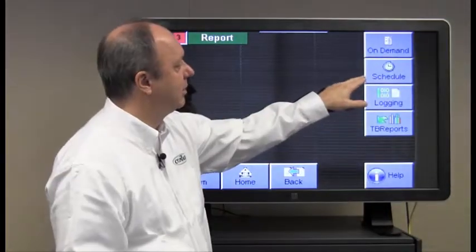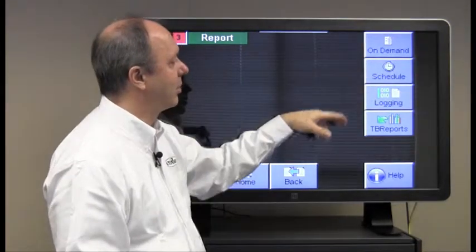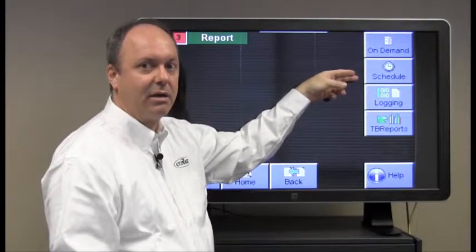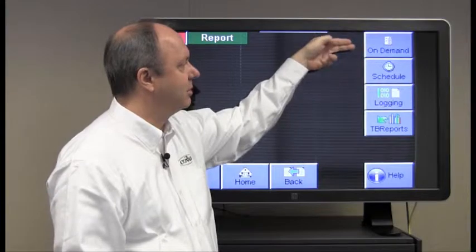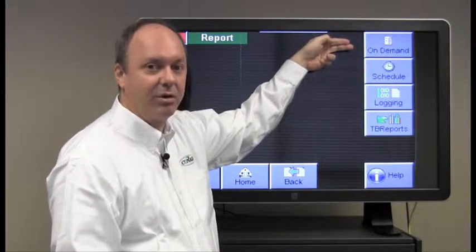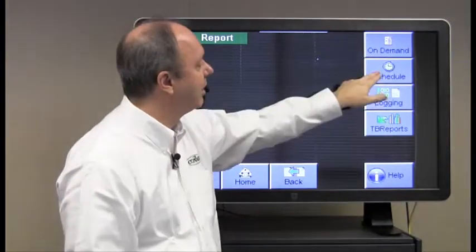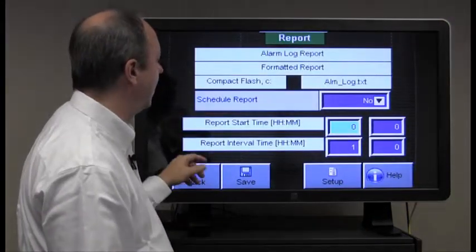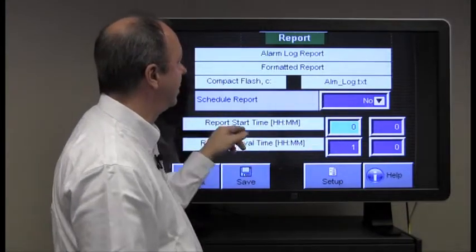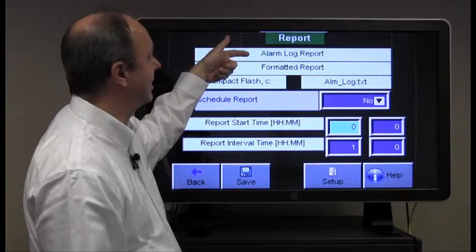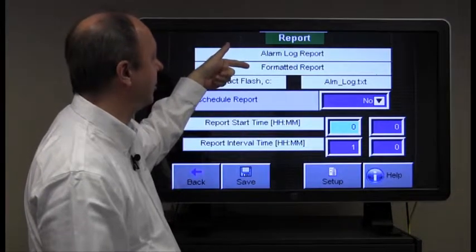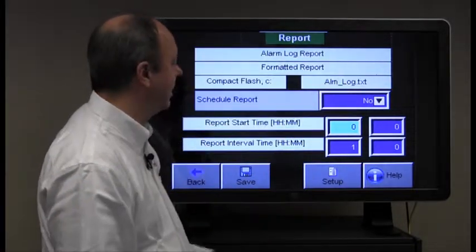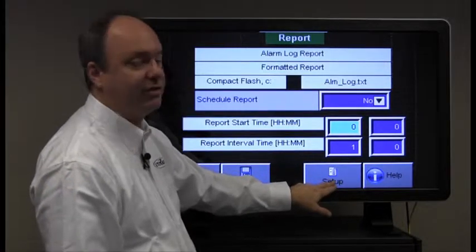So next we'll do the schedule type of report where we want to schedule the start time and how often we'd like a report to come out of the system, as opposed to getting a report immediately on demand, which we already covered. So we press the schedule button for the reports and on this particular page the report type that has been selected is the alarm log and it would be a formatted report. It would go to the compact flash and it would have this name unless we go to setup and choose something different.